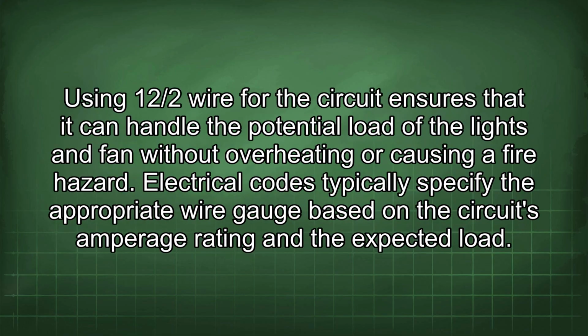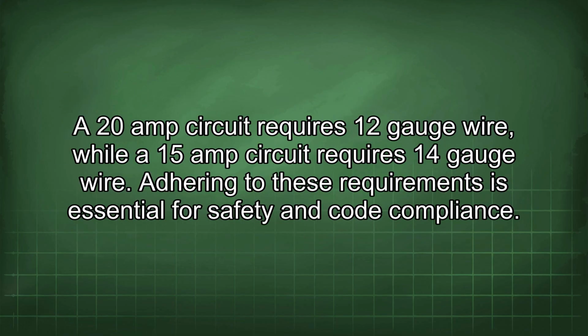Using 12/2 wire for the circuit ensures that it can handle the potential load of the lights and fan without overheating or causing a fire hazard. Electrical codes typically specify the appropriate wire gauge based on the circuit's amperage rating and the expected load. A 20 amp circuit requires 12 gauge wire, while a 15 amp circuit requires 14 gauge wire. Adhering to these requirements is essential for safety and code compliance.